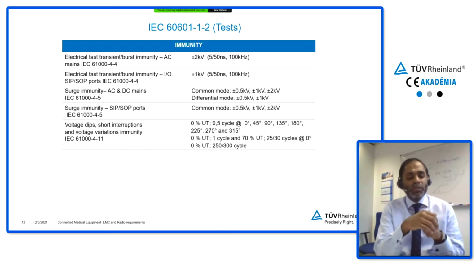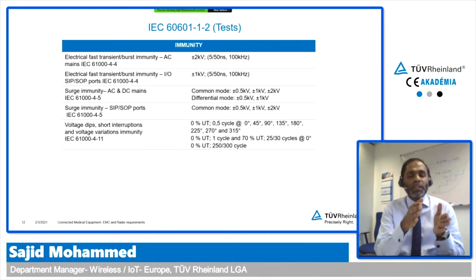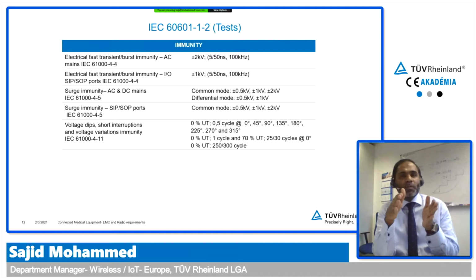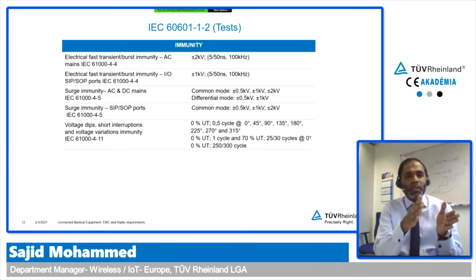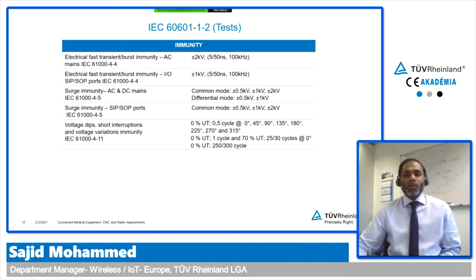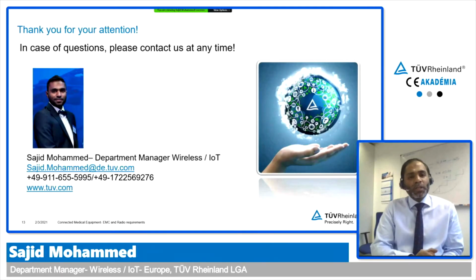IEC 60601-1-2 is the basis of all the EMC tests that are performed on a medical device, and depending on the region, the national deviations of that particular region or country will apply. For instance, the deviations of Europe will have to be applied, along with the deviations of the US and Canada if the intention is to enter those markets. With that, I end my presentation.